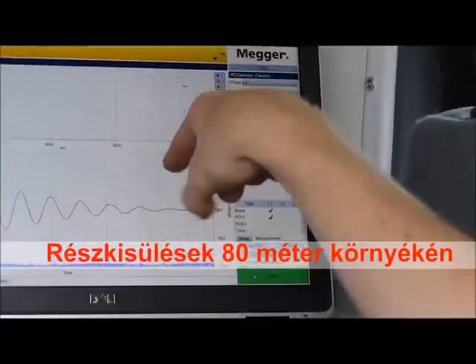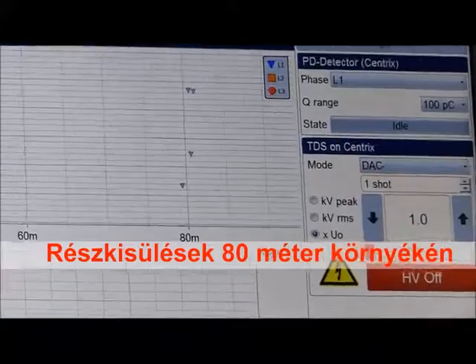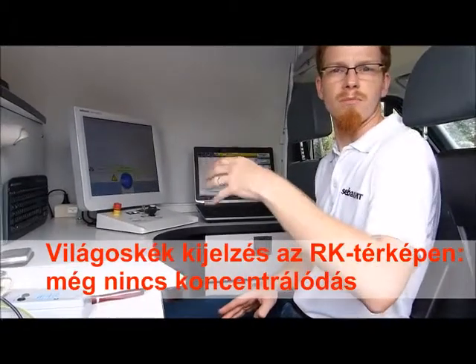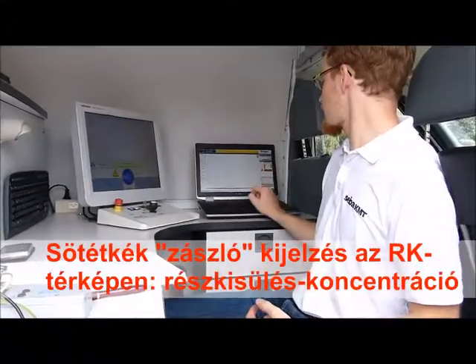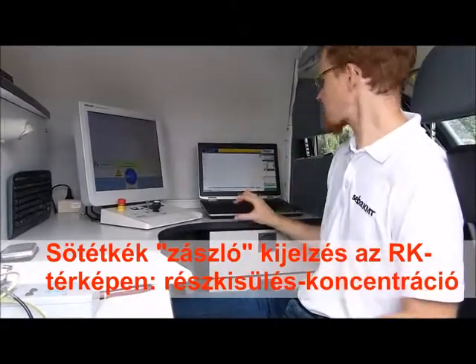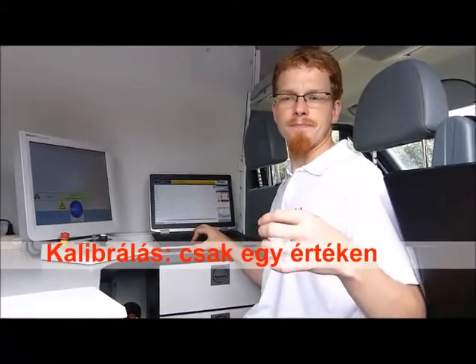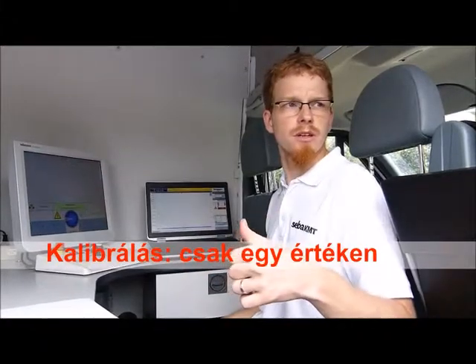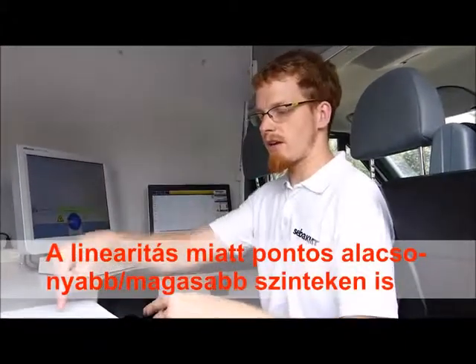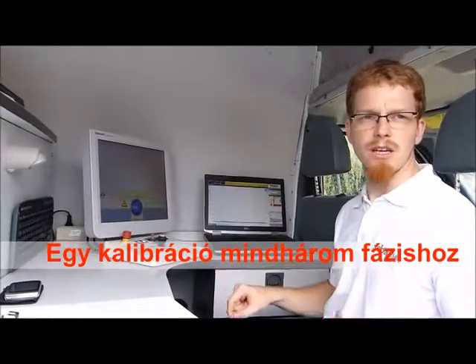Already get more shots here. Safe measurement. There is a concentration, and it turns from light blue into dark blue, and you have the kind of a flag. This system is a digital unit, and we only have to calibrate once, and it's linear. So even when we have only one calibration level, it's giving us accurate levels for the higher partial discharge level and also for the lower partial discharge levels. And similar like with the OWTS, you can use the one calibration range for all three phases.